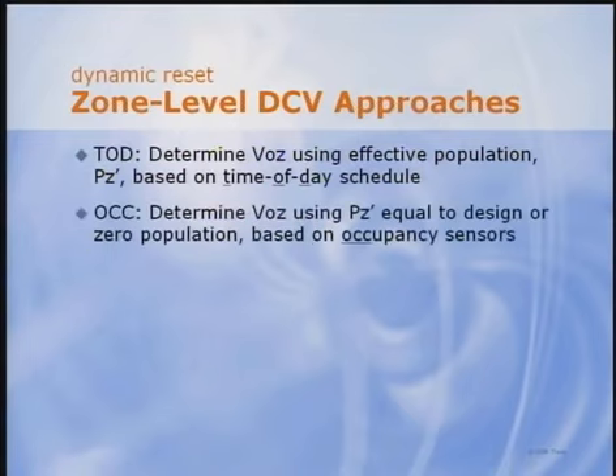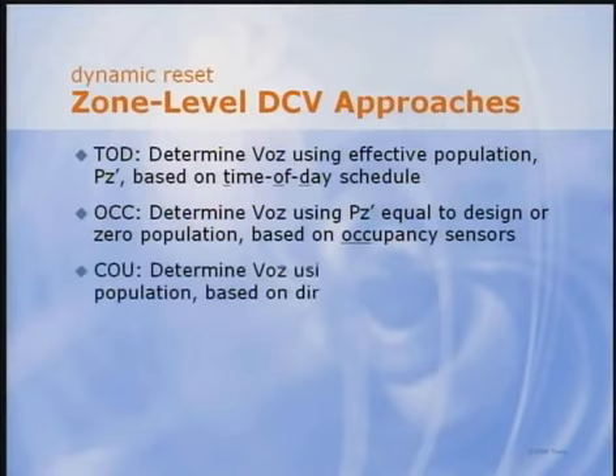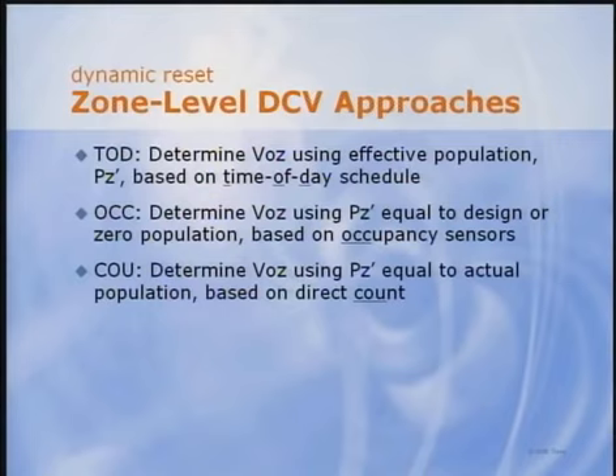Binary occupancy sensors can be used to register either design or zero population. They can be used in any zone, but are probably best suited to small conference rooms, private offices, museum display rooms, and so on. And it's possible to actually count people in some zones based on ticket sales in movie theaters, for example. However it's determined, the ventilation system controller uses the current zone population to solve equation 6-1 for the zone outdoor airflow currently required. Then the controller can take appropriate action, which usually means opening or closing the outdoor air damper.